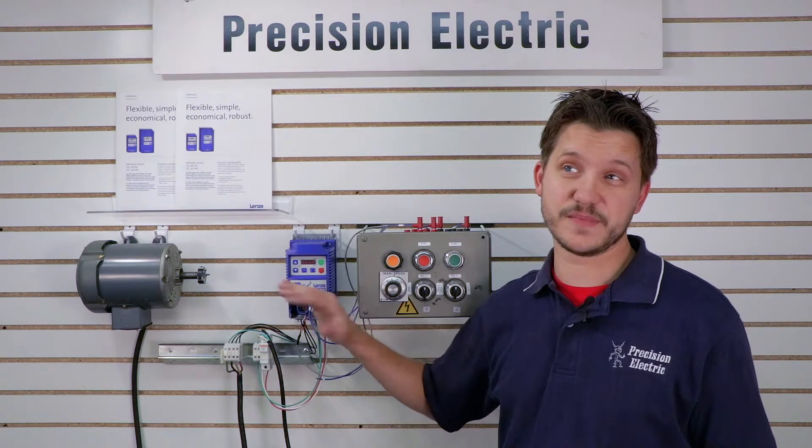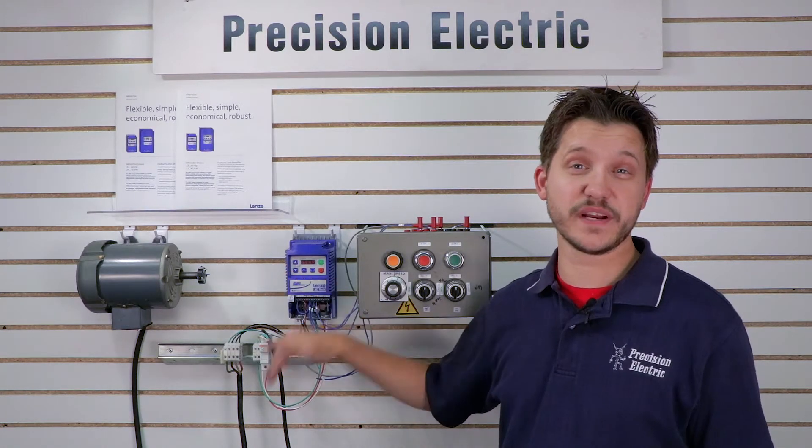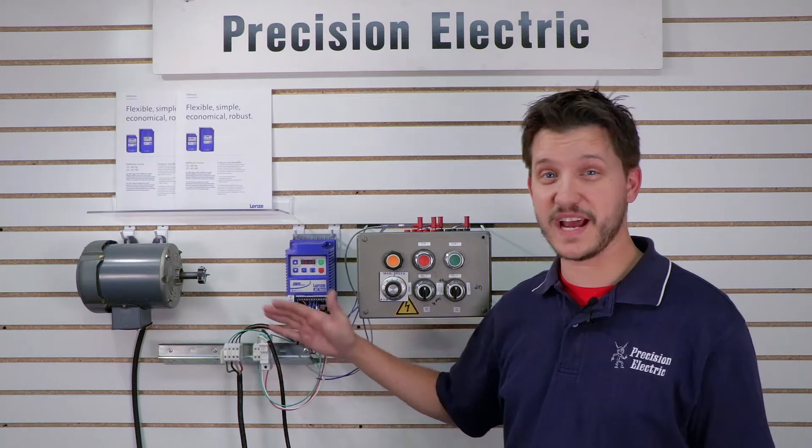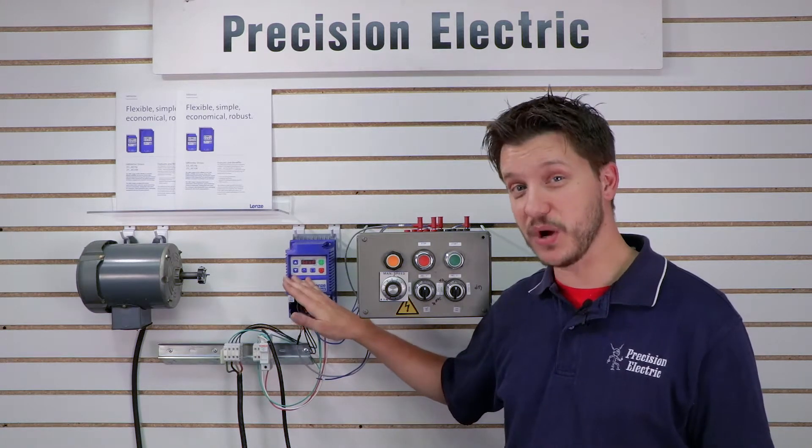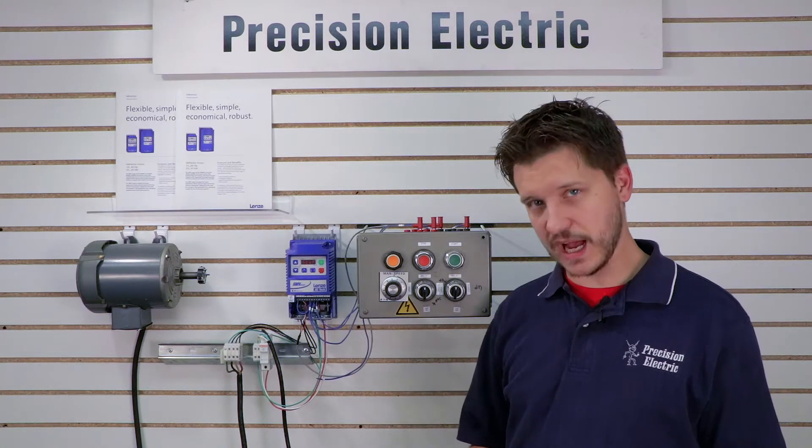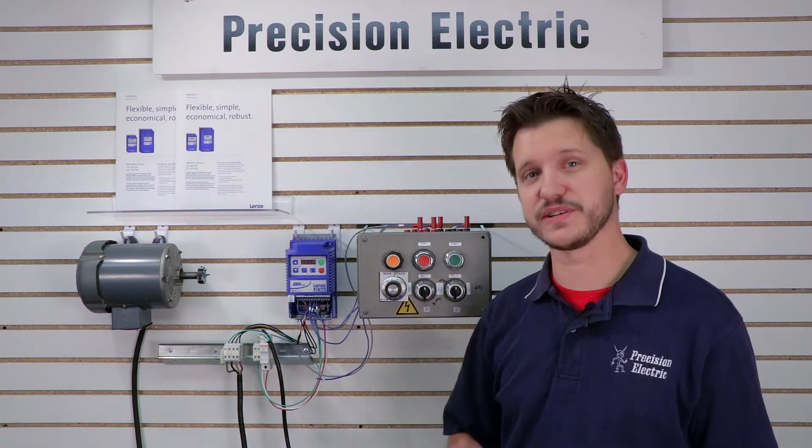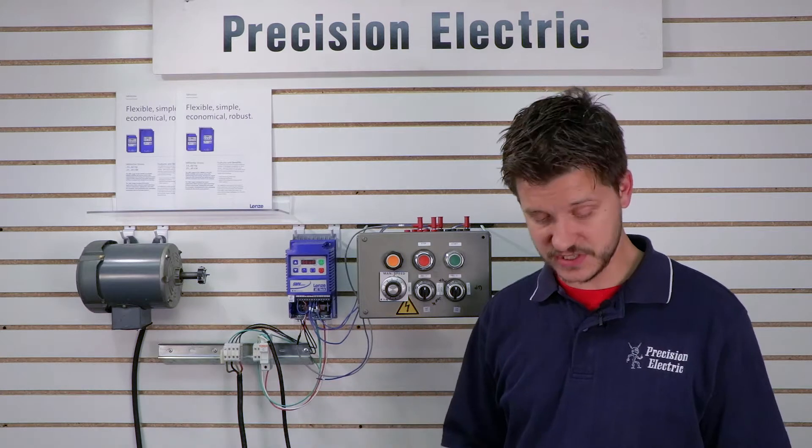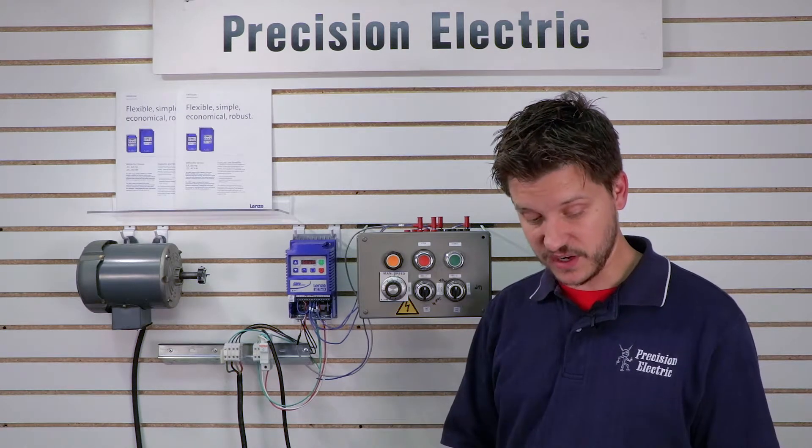If that doesn't fault it out, then you want to reconnect your motor. You can try running it again. If it happens again, then you probably want to get your motor tested to make sure that your motor isn't shorted. So those are the three most common faults that you're going to get when you actually are dealing with the SM vector variable frequency drive. There's a lot of other ones on here.